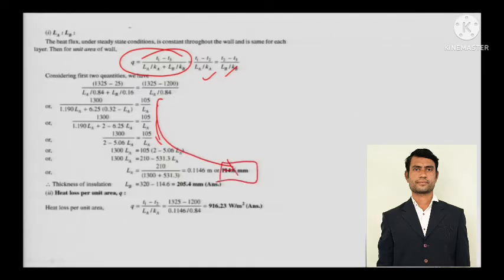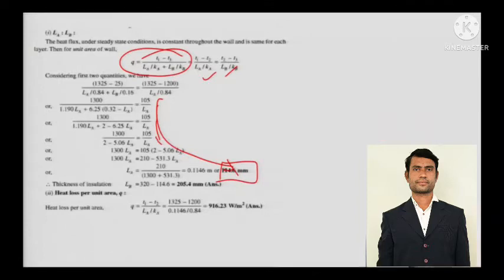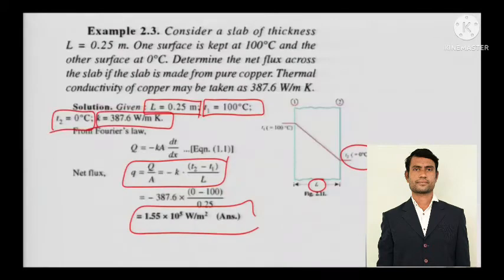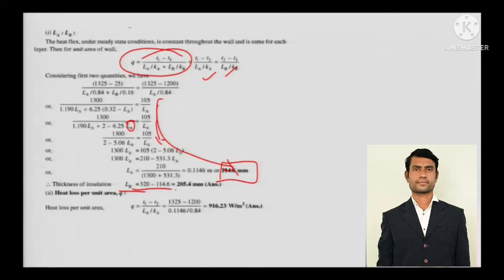When LA is unknown and everything else is known, you can calculate LA — the thickness of the fire brick. The thickness of the insulation LB will be 320 mm minus LA, so you will get LB.